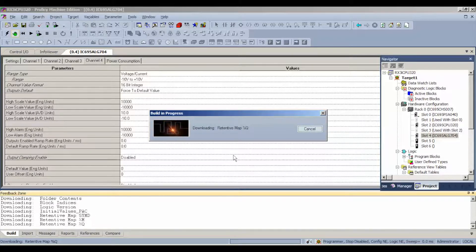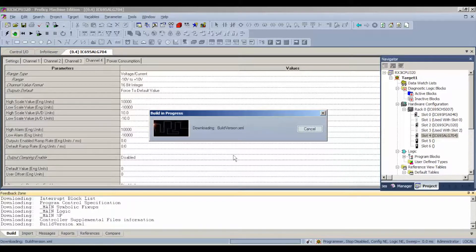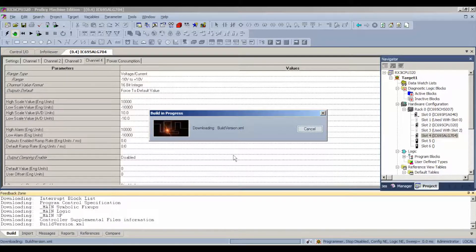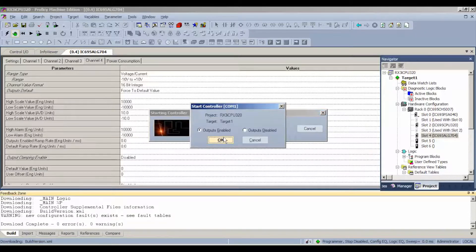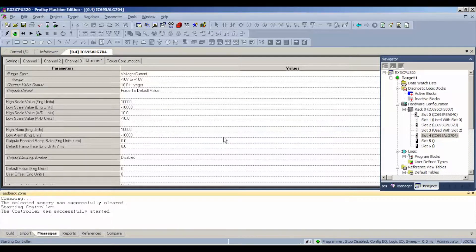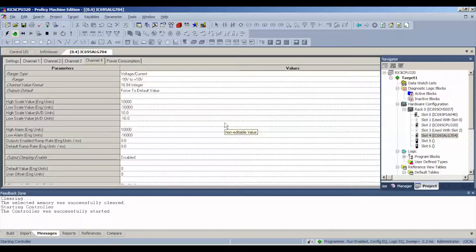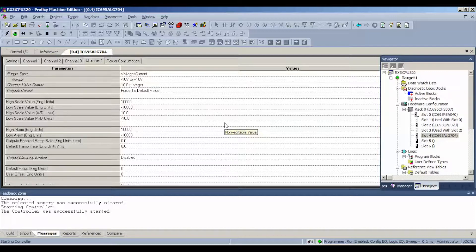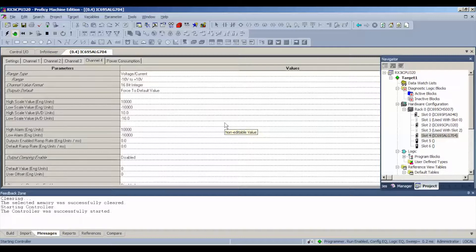Now download will only take a minute, and once it's done, it's going to allow us to turn on the outputs like so. Your processor should be in run mode at this point once you've okayed the turning on or enabling the outputs. If your processor is not in run mode at this point, you may want to take a look at your status, make sure your configuration and your logic is equal, you haven't left anything out.